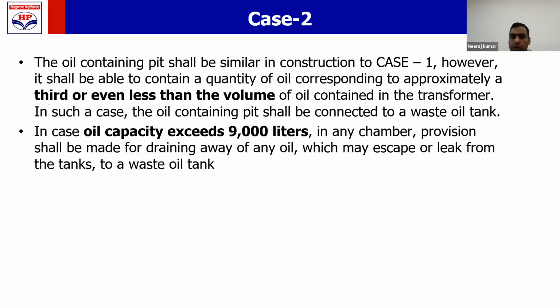वो ऑयल जाएगा कहाँ पे जो निकलेगा? उसके लिए हमारे पास है waste oil tank. We should connect the oil containing pit with the waste oil tank. इसमें एक exception है. In case oil capacity exceeds 9,000 liters, the provision shall be made to drain the oil away from the oil which may escape or leak.